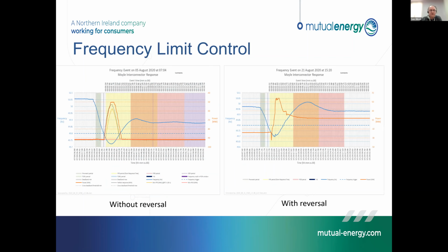I mentioned our ancillary services. These couple of graphs demonstrate our frequency limit control. Where we provide up to 100 megawatts of frequency limit control on the left-hand side without reversal, you can see that we have a very, very clean waveform matching the frequency drop really well.